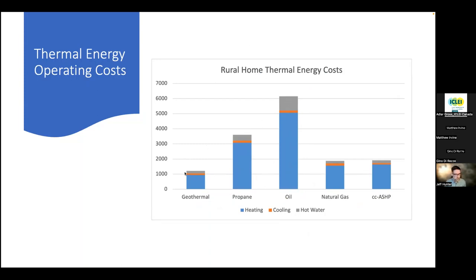Now, I think I saw somebody mention a question about Greener Homes and payback and how that factors in. The Greener Homes Program obviously is providing funding directly to consumers to retrofit their homes from fossil fuel to an electrified system. If you look at the difference in cost and operating cost, and let's just compare a geo to an oil system, there's a savings there. In this case, it's not quite $5,000, so it's significant. And so that's where it ties back to what Matt had said in his first presentation with respect to five-year paybacks. If you're saving close to $5,000 a year, you can pay back a system in a relatively quick amount of time. Propane is the same case. We're saving about $2,400 a year.